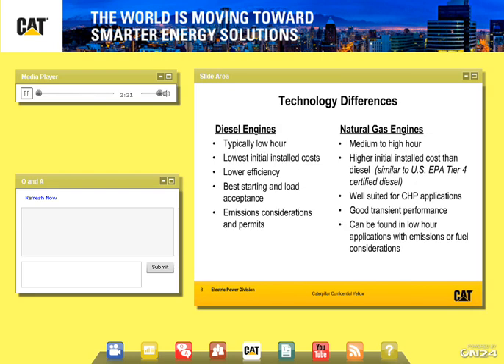I wanted to open up with high-level technology differences between diesel engines and natural gas engines. As a level set with everybody on the phone, diesel engines, typically low-hour solutions, lowest initial installed cost, tend to have lower efficiency than natural gas engines. They do have best starting and load acceptance characteristics.